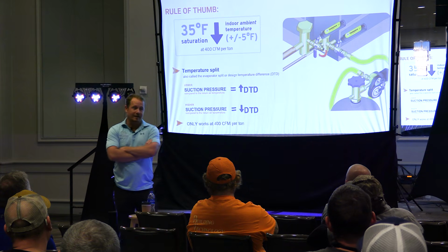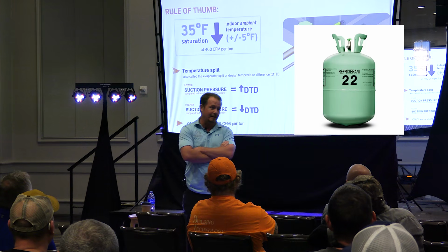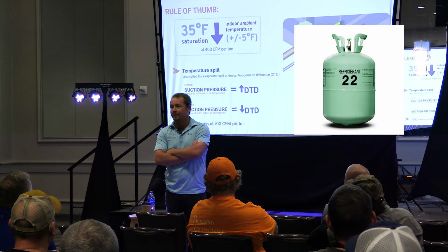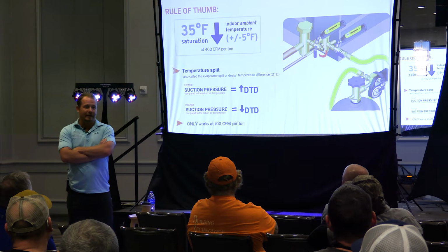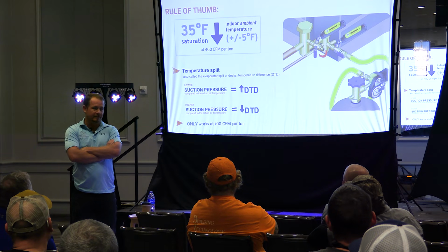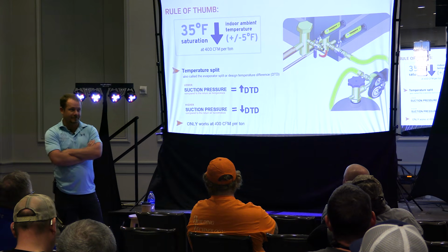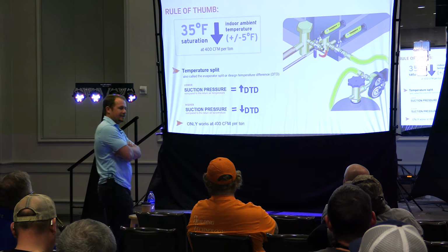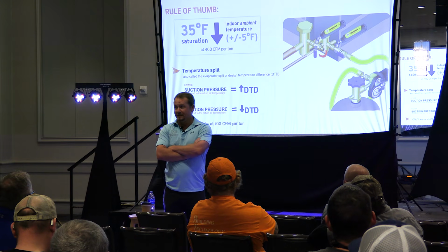There's a couple little tricks with R22 that I don't know. I think it was just God smiling on tradesmen at that time. Maybe they'd been especially good for a couple decades. I'm not sure. But the same thing was true with heat pumps. You would work on a heat pump and you'd be like, well, it's an R22 system running in heat. What should your suction pressure be on an R22 system when it's 30 degrees outside? About 30 PSI. It's like, wow, that's kind of strange, isn't it?